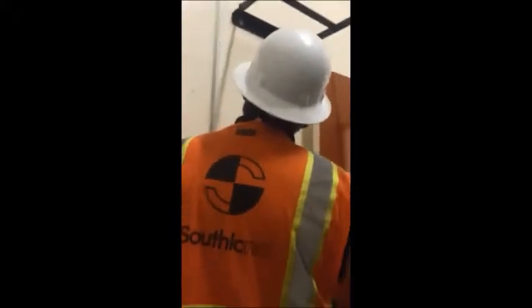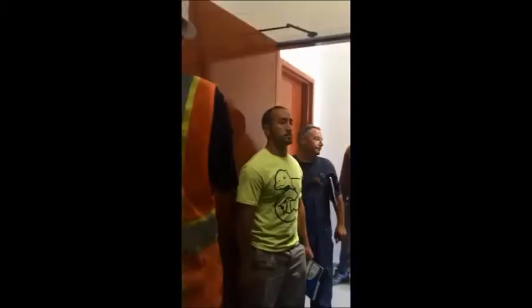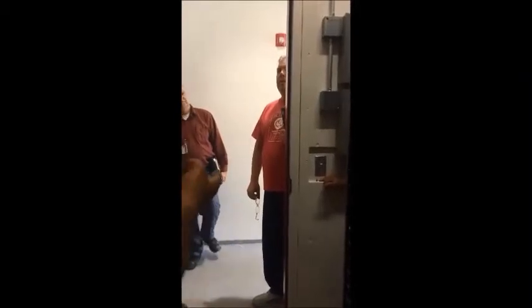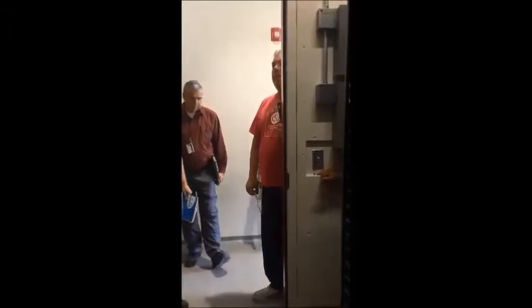So again, condensate pump, discharge temp sensor, thermostat, MNet. That's all MNet. Are those standalones, or are they on the network and talk MNet as well? They don't. It's a power line carrier, fed through the fourth wire that's part of their design. You have a 208 single phase, a ground, and then a transmission line, which is basically a power line carrier. Red, white, and black.